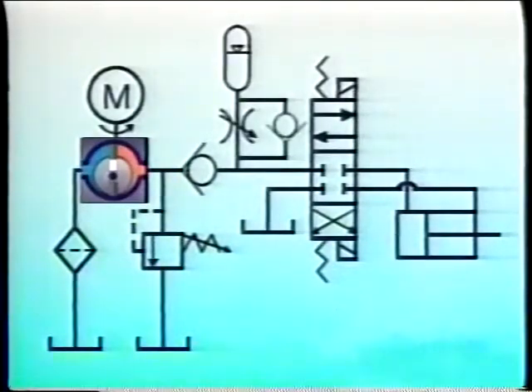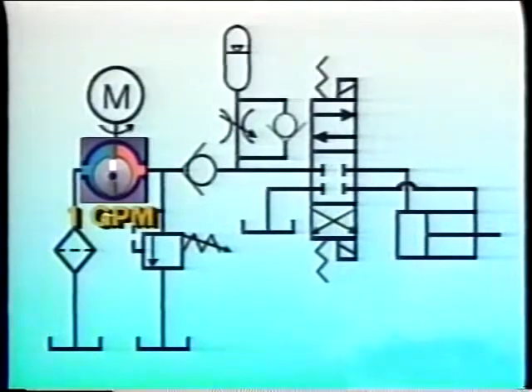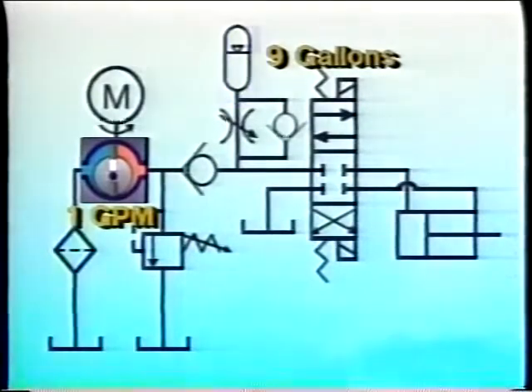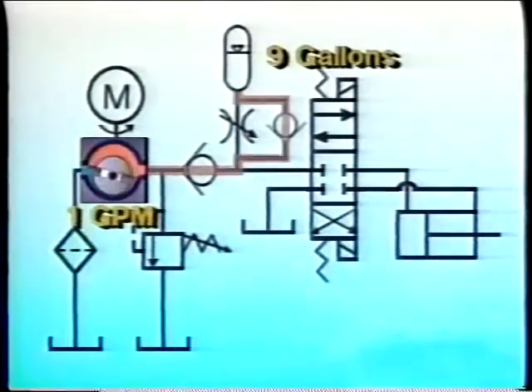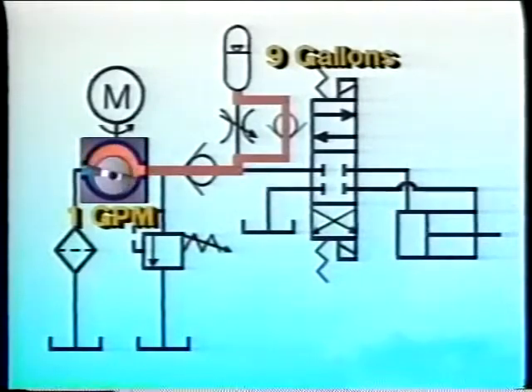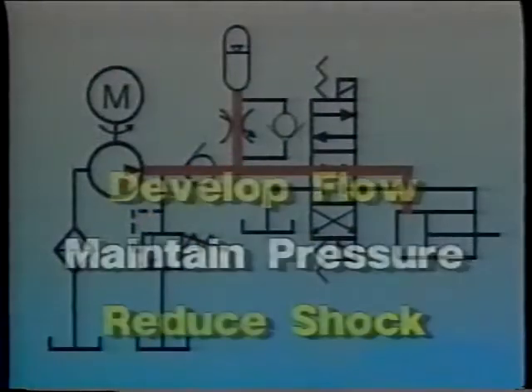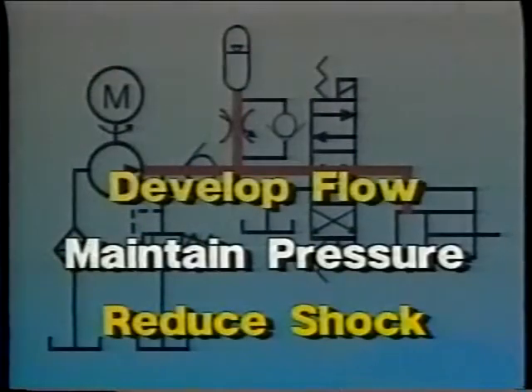The same work could also be done with a less expensive one-gallon-per-minute pump and motor, and with an accumulator that has a working volume of nine gallons. For nine minutes the pump would store energy as pressurized fluid in the accumulator, then supplement flow from the accumulator during the 10th minute.